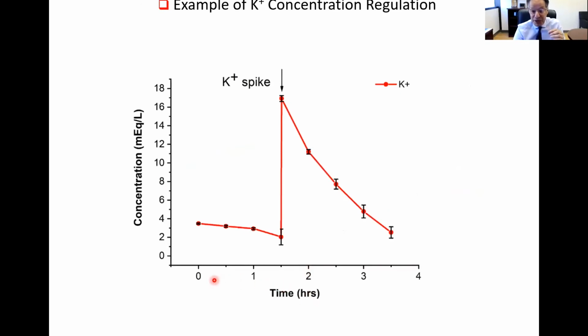This is an interesting experiment showing the device's capability to regulate potassium concentration. We put in a solution with potassium of 4, then spike it up to 17 millimolar, which isn't physiologic, and watch the device transport the potassium back down close to its original range. Here it was done over 2.5 hours, but it can be done much faster as needed. We have a feedback system where potassium is sensed, and the computer can alter the device's functionality to change the rate of transport and return it to normal more quickly if needed.